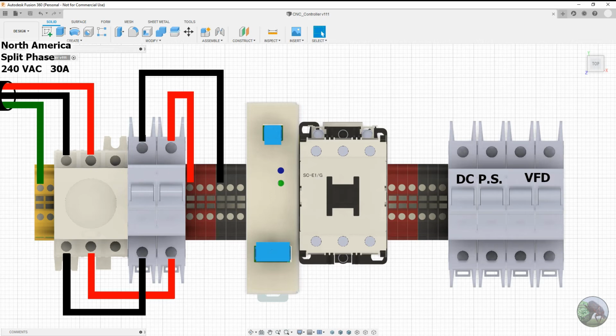And so this bus feeds items that need to be powered all the time. And in my case, there's just 3 items. It's the 24 volt DC power supply, which is right next to it, that controls the latching circuit that runs the contactor. And the Stego enclosure fan, which moves air to cool everything in the enclosure. And then lastly, the ammeters that are on the front panel. And I chose to include those 2 items here because I wanted both a visual and auditory reminder of when power was being energized within the enclosure.